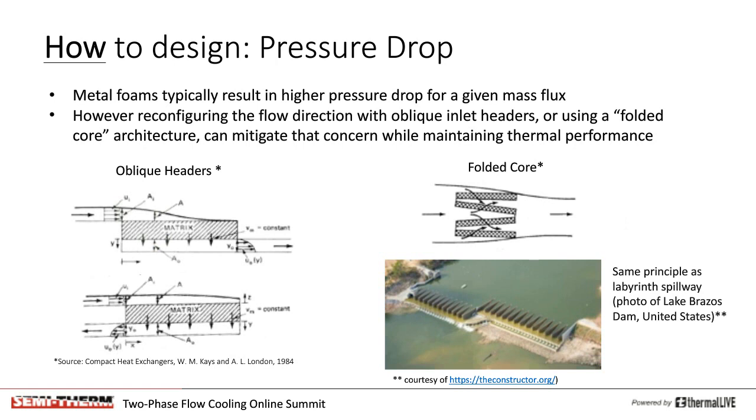Yet more conventional finned cold plates and heat exchangers do not usually resort to such architectures, and indeed, in many cases, they are precluded from doing so due to the unidirectional nature of fins. Therefore, when one is considering a drop-in replacement with foam, it is useful to think out of the box in terms of form factor and make best use of foam's advantages. Also note that it is quite straightforward to model the 2D and 3D effects in these designs using conjugate heat transfer CFD models with a porous media approach.